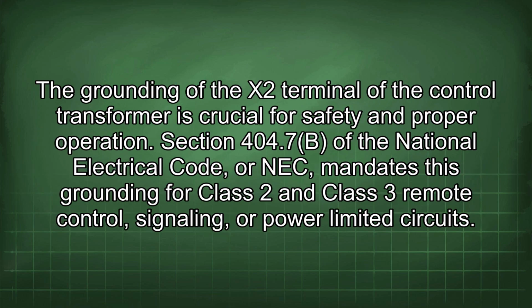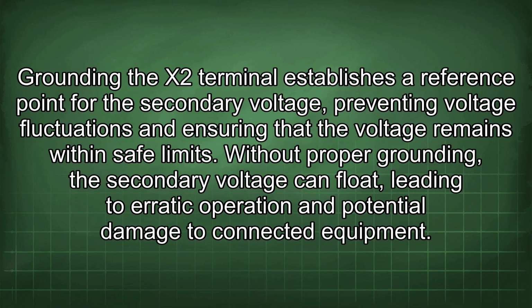The grounding of the X2 terminal of the control transformer is crucial for safety and proper operation. Section 404.7b of the National Electrical Code, or NEC, mandates this grounding for Class 2 and Class 3 remote control, signaling, or power-limited circuits. Grounding the X2 terminal establishes a reference point for the secondary voltage, preventing voltage fluctuations and ensuring that the voltage remains within safe limits. Without proper grounding, the secondary voltage can float, leading to erratic operation and potential damage to connected equipment.